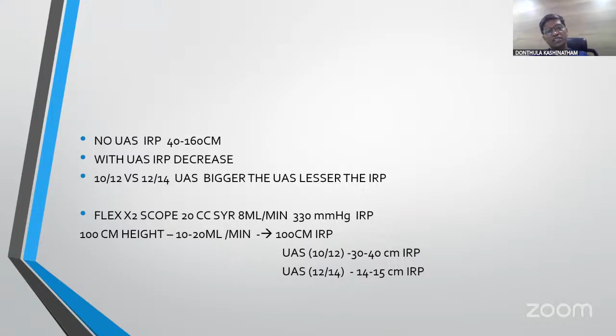At the same time, whether you are using a fiber in the working channel or just doing diagnostic ureteroscopy also matters. Most of the time we are breaking stone, so most of the time the working channel will be engaged with the probe. With the probe in situ, raising the pressure will be very difficult because the flow won't be that high. So these are the main important factors that raise the pressures. Inflow and outflow balance should be there, then you will control the intrarenal pressure.